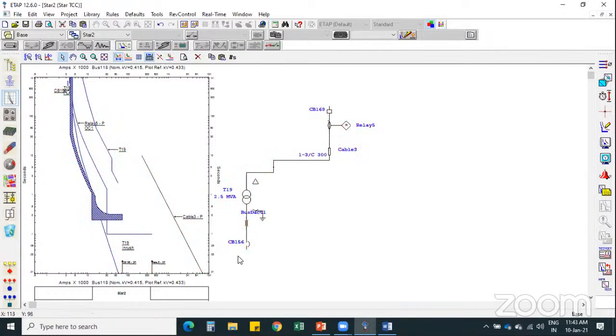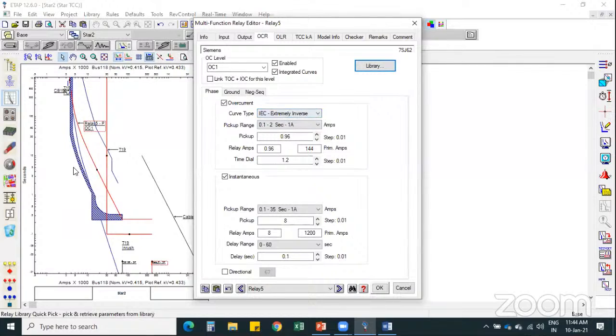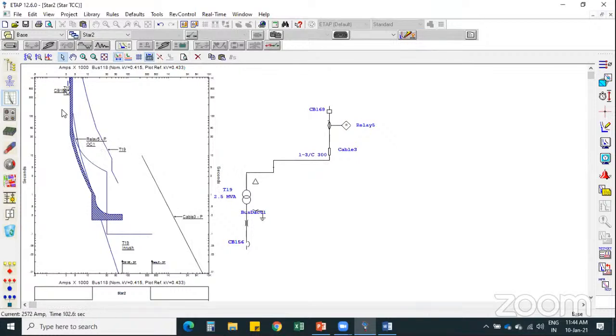This is the curve of this LV circuit breaker, and this is the curve for this HT transformer primary side relay. The curve should be such that it should match the tripping command of this LV circuit breaker. Now, if we are choosing this normal operation curve, then what will happen? Then it will overlap this relay. You can see here it is overlapping the curve with this LV section. So this is not properly coordinated.